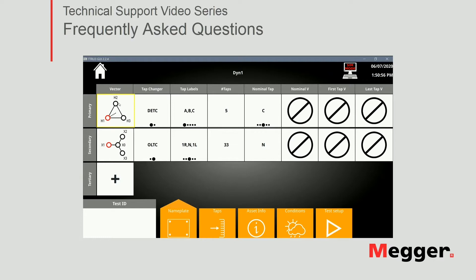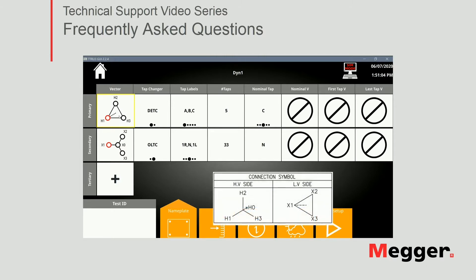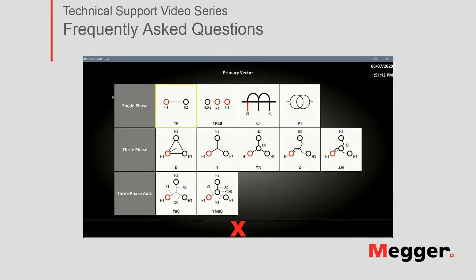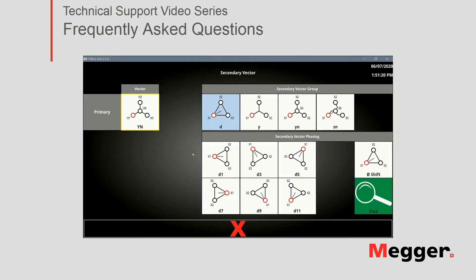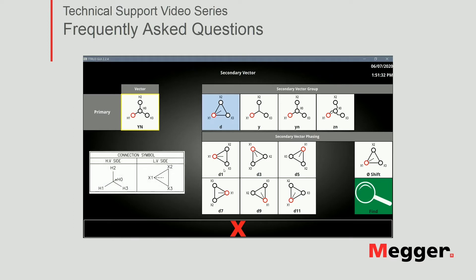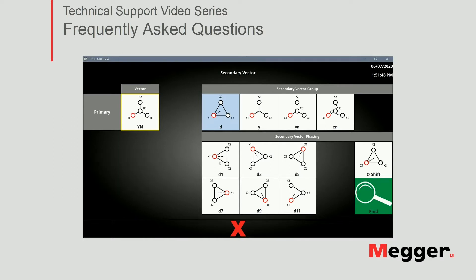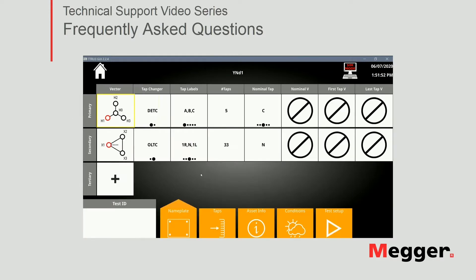Let's start by filling out or telling the software the vector configuration of our transformer. Looking at our nameplate, we can see that we're going to be testing a YND transformer. When I click the primary vector, I select YN and then we have a delta. The software will offer the possible phase shift configurations. If you're familiar with the different phase shifts, you can directly select it. If not, notice that the diagrams are rotating accordingly, so you just have to match exactly the same orientation as the one on your nameplate. Go ahead and click D1 — that matches exactly what I have on my nameplate.